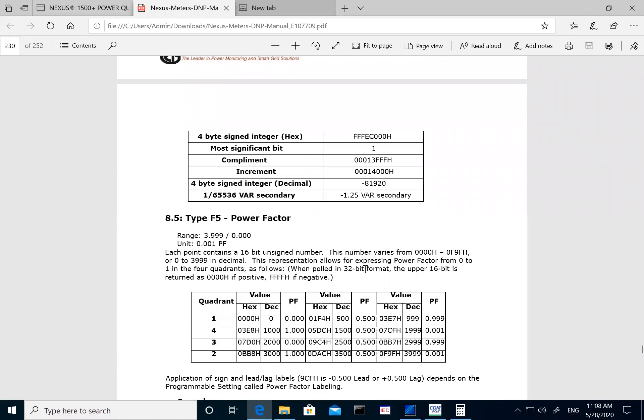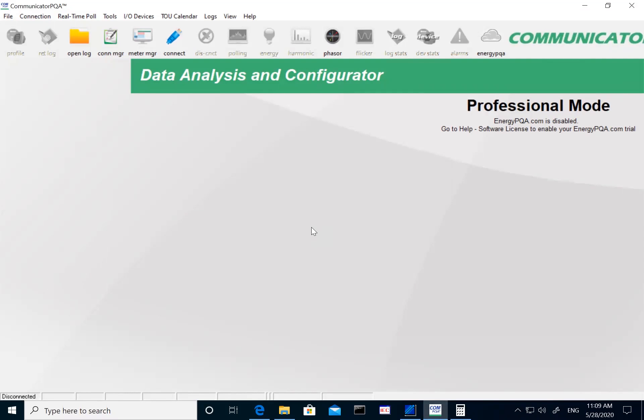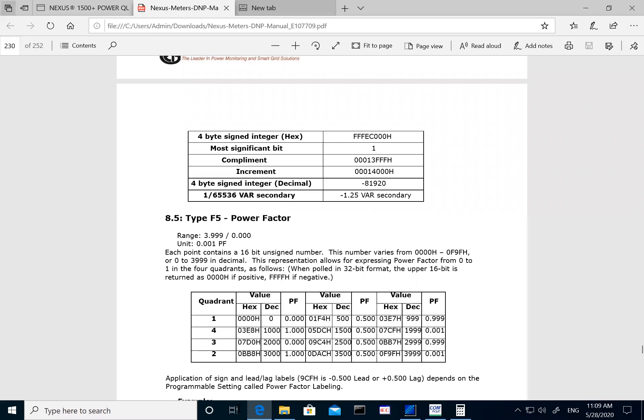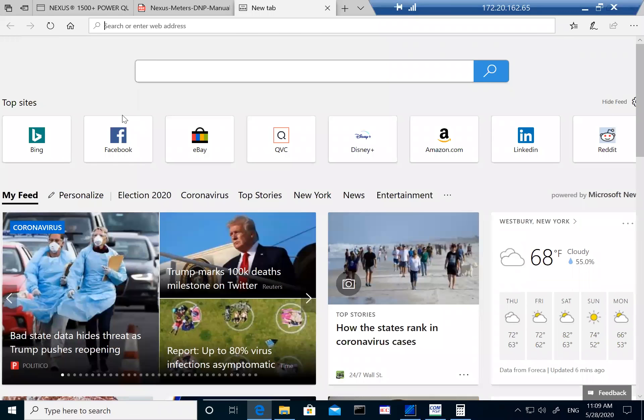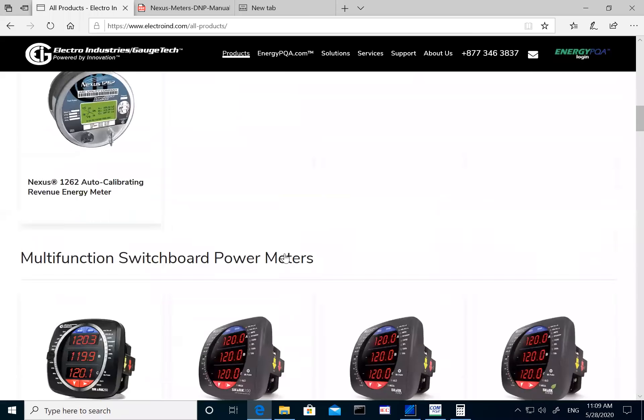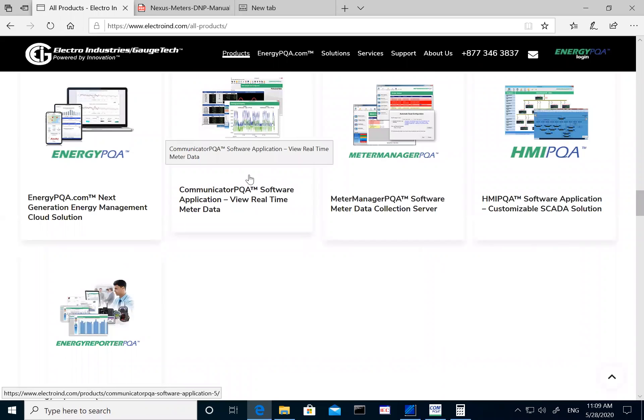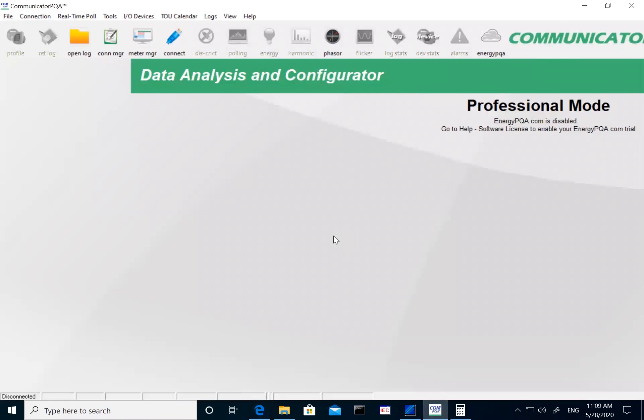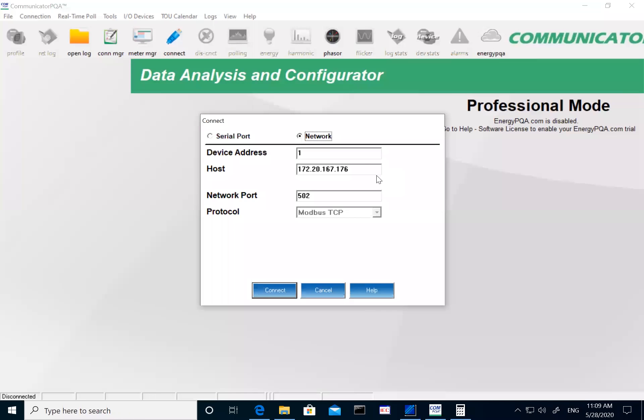Now let's go into programming the meter profile. To program the DNP settings on the Nexus 1450 and 1500 series, you use our Communicator EXT software, which you can download from our website under Products in the software section. You can use it to connect to the meter, program all the meter settings, and download logs. Since we are focusing this webinar on DNP, I'll skip to the DNP section. First I hit Connect, then put in the IP address of the meter and hit Connect.